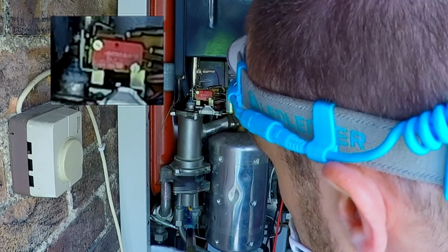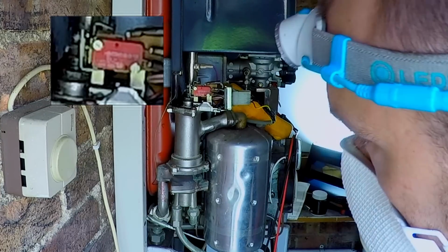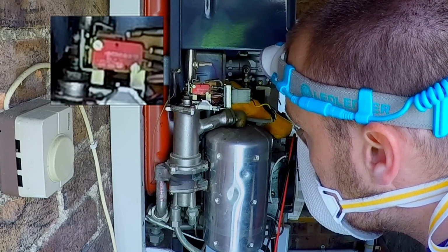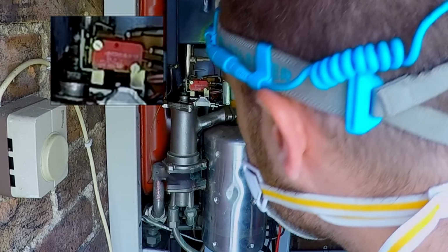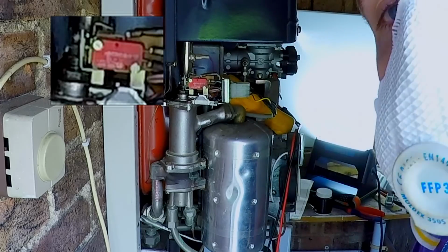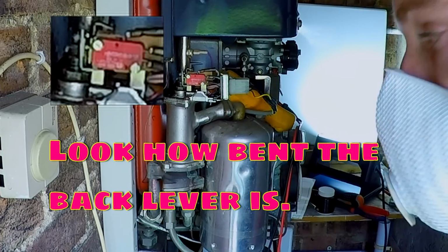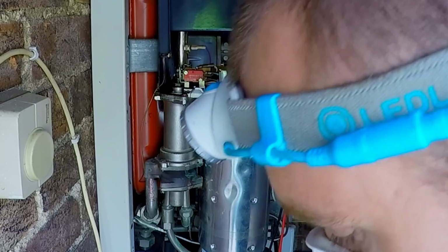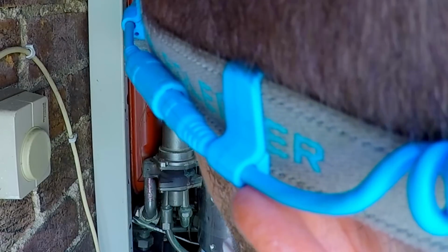There we go. See that? Got it working. Just got to hope the boiler can maintain it and keep it working. So it's clicked the front one and it's unclicked the back one. Bit of heat applied to the wax part, and as you see, WD in the top. Hopefully get the spindle moving again properly, because that hasn't worked properly for a little while, I would have thought.